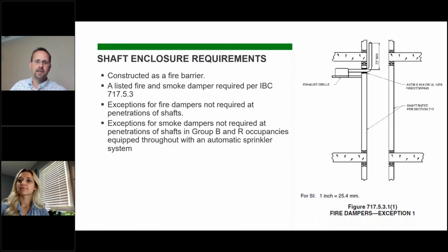The way that works, the subduct in theory is that if fire does get through on that one floor, it'll prevent it passing into the shaft and to other areas. And so that subduct could go into the shaft, and that shaft is open, and that shaft carries the airstream. Or if you had a duct in the shaft, that subduct could go into that other duct and extend vertically 22 inches. The other portion of that is that the shaft needs to have an exhaust in the shaft that provides, the code says, a continuous upward airflow in the shaft itself.